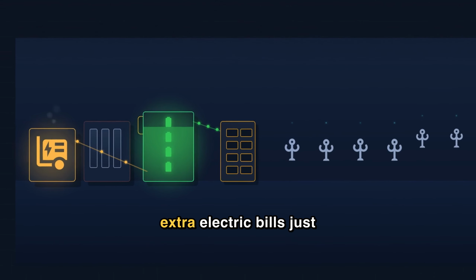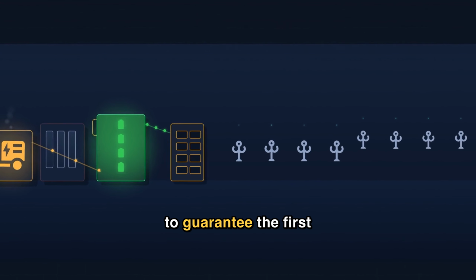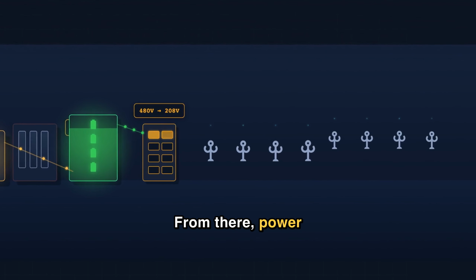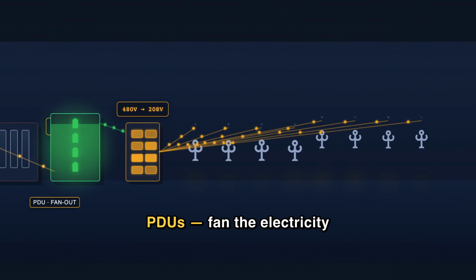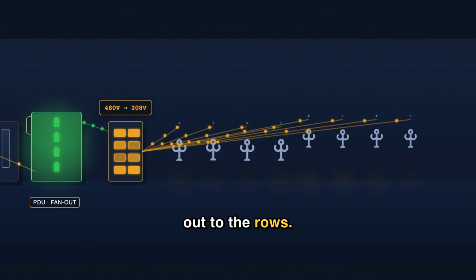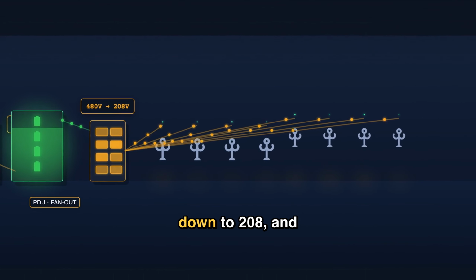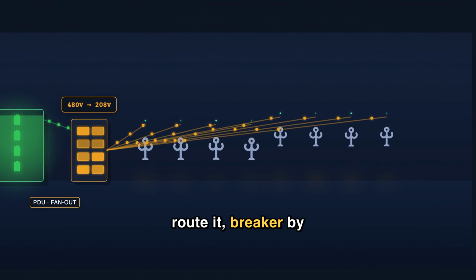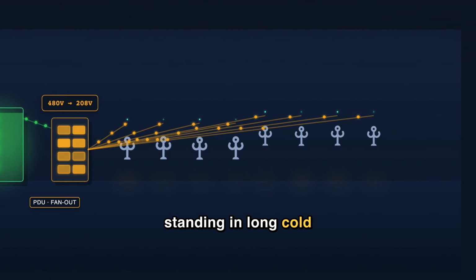It's like paying 2 extra electric bills just to guarantee the first one never drops. From there, power distribution units, the PDUs, fan the electricity out to the rows. They split 480 volts down to 208, and route it, breaker by breaker, to the racks standing in long cold aisles.